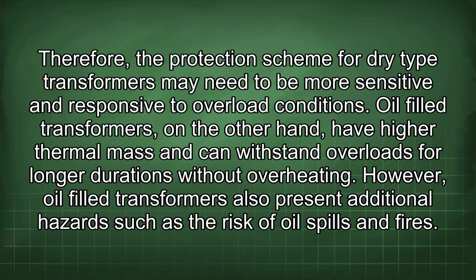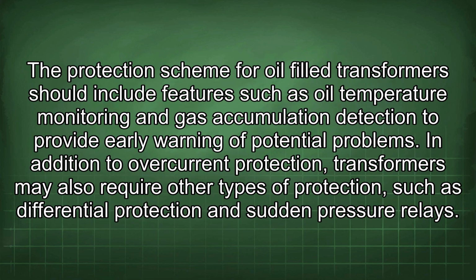Oil-filled transformers, on the other hand, have higher thermal mass and can withstand overloads for longer durations without overheating. However, oil-filled transformers also present additional hazards such as the risk of oil spills and fires. The protection scheme for oil-filled transformers should include features such as oil temperature monitoring and gas accumulation detection to provide early warning of potential problems.